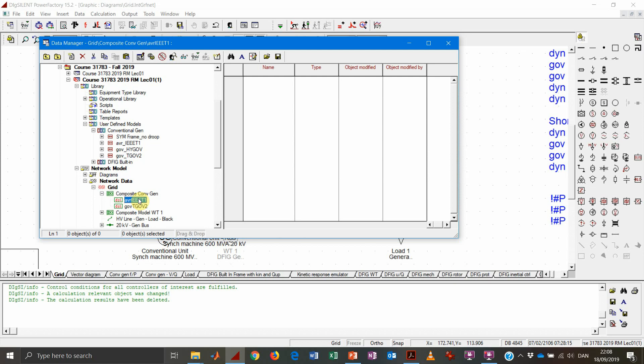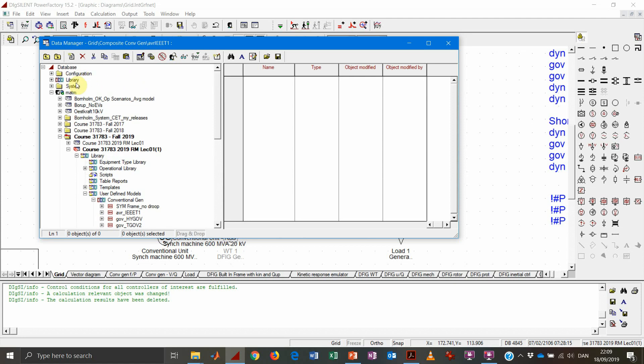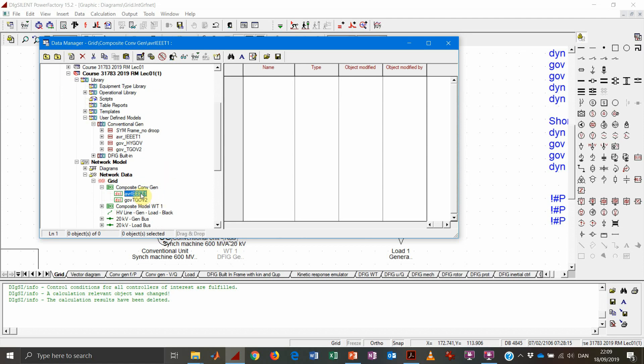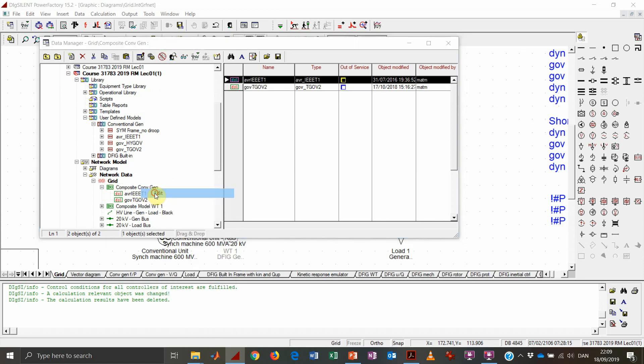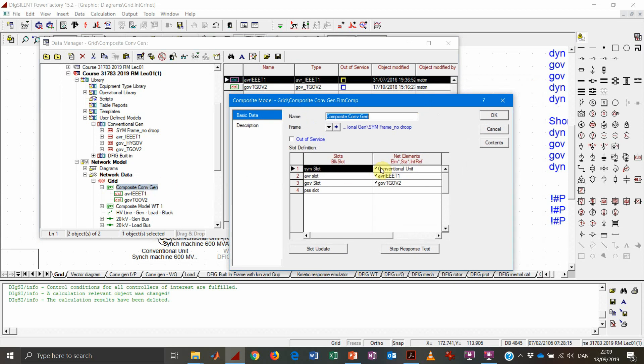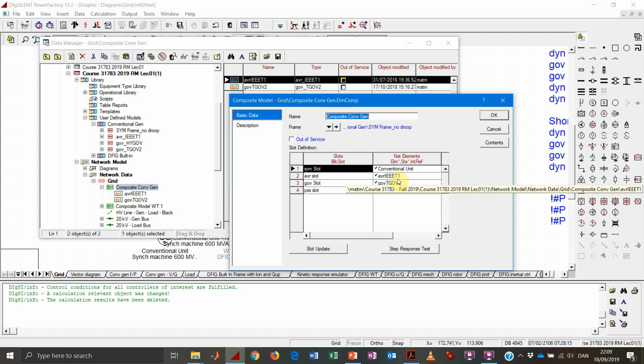It's always important to make sure that when there are references to dynamic models — or to types in general — they are pointing to types located in the local library and not in the main library. If you copy-paste the project and bring it to another computer that may not have the same general library, PowerFactory will not be able to find the type that your AVR or governor are pointing to. A useful feature is that right-clicking on the composite shows a table reporting which elements and common models are used for that composite model.